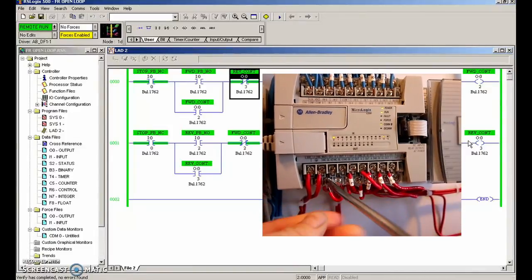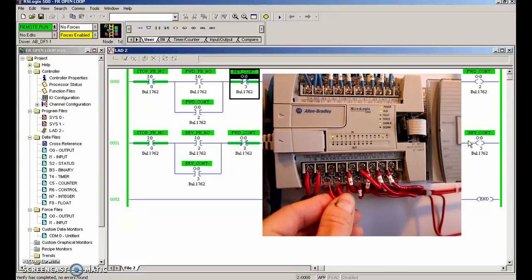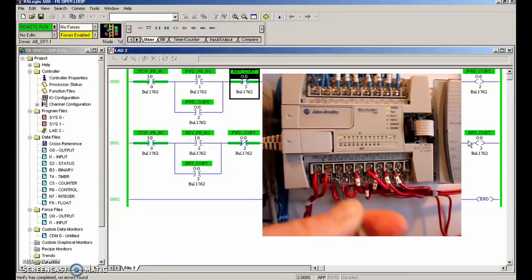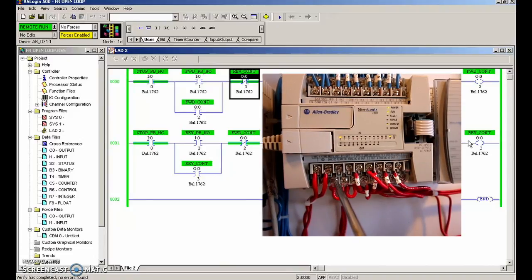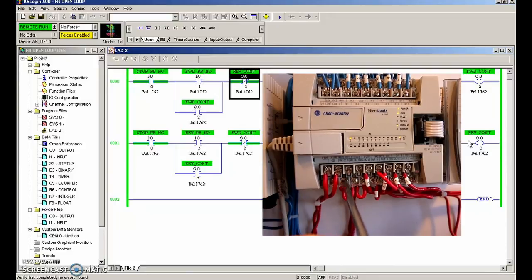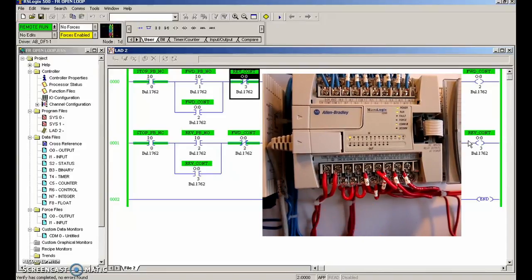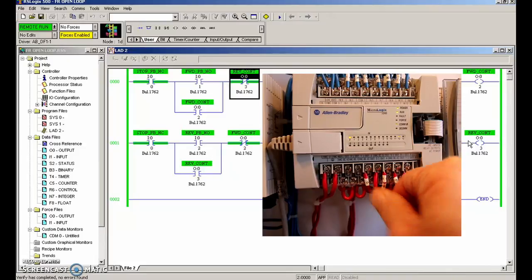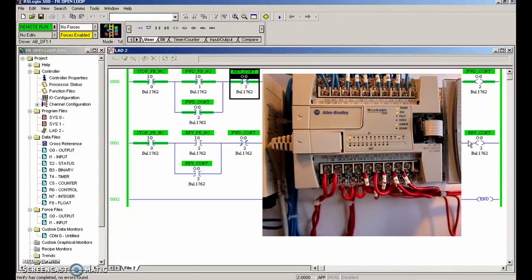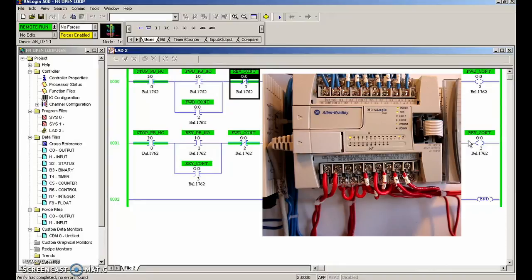If your outputs were 120V you definitely don't want to be putting your fingers in here while the PLC is live — always best to turn off the PLC while doing this. I've at least turned off my outputs while making this last connection. Make sure you back off the terminal first to allow room for the conductors — a lot of times in the shop you guys forget to back away the terminal and then crank down and strip it because there's no conductor there. All right, let's make sure everything's working — forward, beautiful, stop, reverse, beautiful.